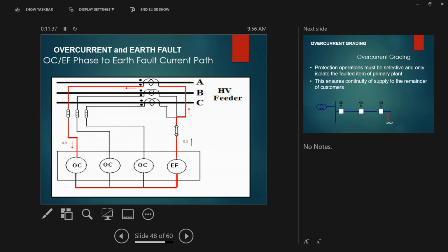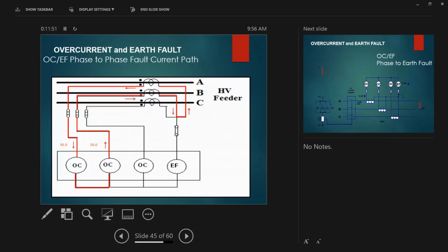You can also inject on two phases with opposite direction. Because as Francis already discussed on the previous one, if you inject two opposite directions, it will cancel out. That's why when you see the test results, sometimes we have overcurrent phase A-B, B-C, C-A, because we need to avoid tripping the earth fault. So we do the combination A-B, B-C, C-A, just to trick the relay, if you don't want to disable this.